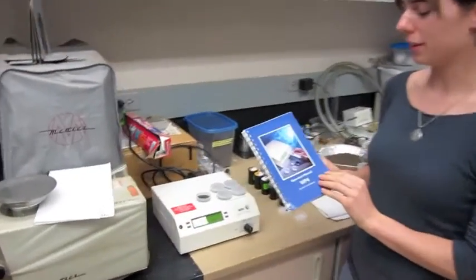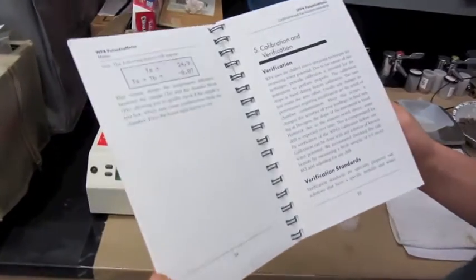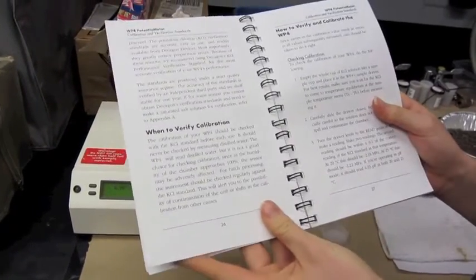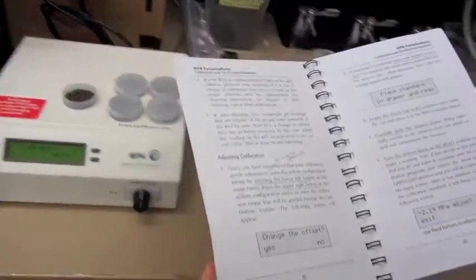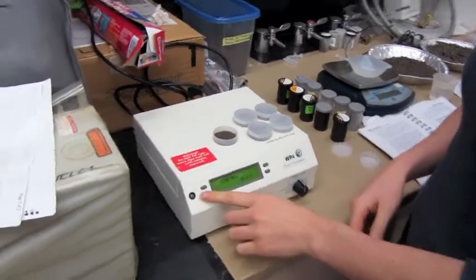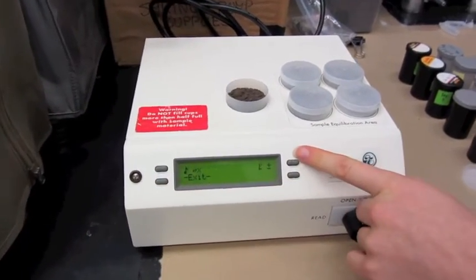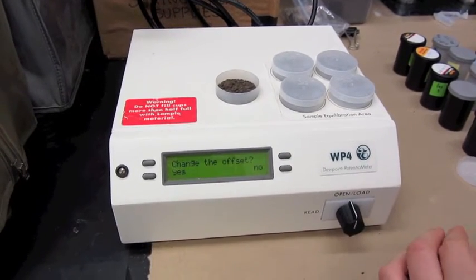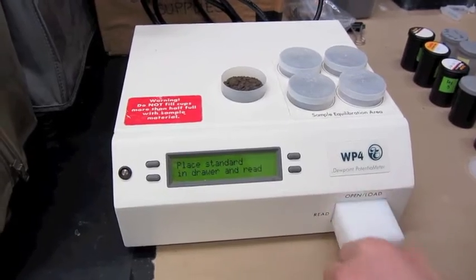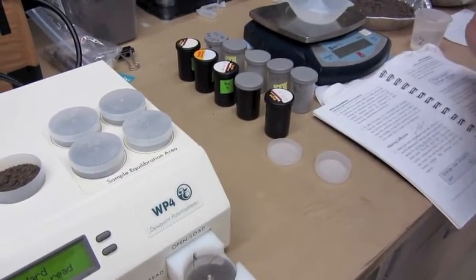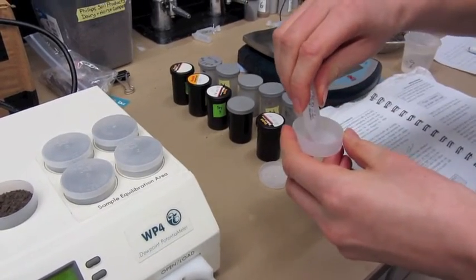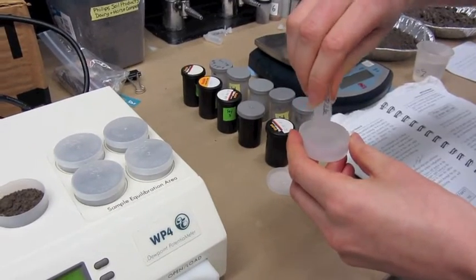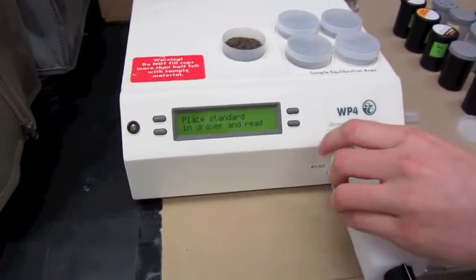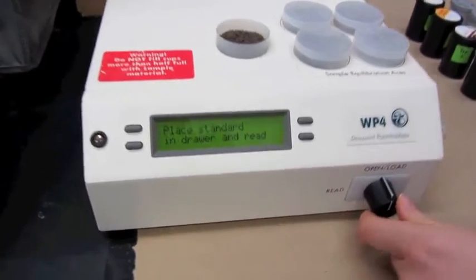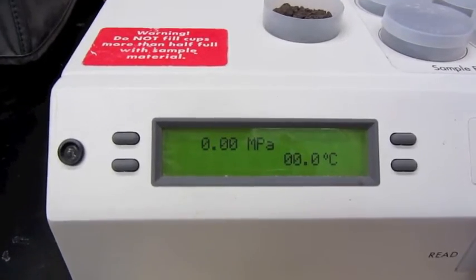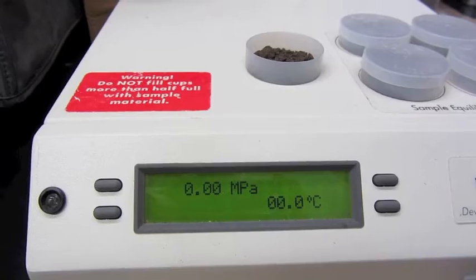Go to page 25 of the operator's manual for calibration and verification, or skip to page 28 and follow my instructions. The lower left button brings you to the root menu, and then the top right button lets you change the offset. So yes, change the offset. Then place a vial of potassium chloride into the sample container. Carefully. And close the drawer carefully. Then turn the knob to read.